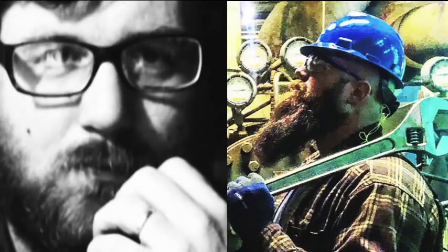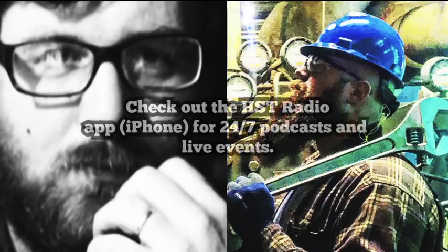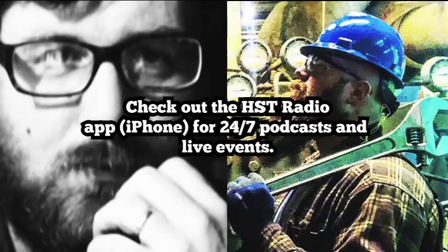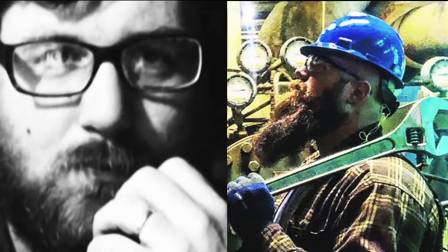How does it work? Well, in this particular school, there was one big air handler and several fan cooling units throughout the building. Yes, exactly what you said as far as reheats. That's why the boiler runs 365 a year, because they run hot water constantly to potentially temper the air for dehumidification purposes. So where you have that water set at 49 degrees, there's going to be plenty of times where that's below our dew point and helps with dehumidification. In order to temper that air, we introduce that boiler water before it exits the supply.